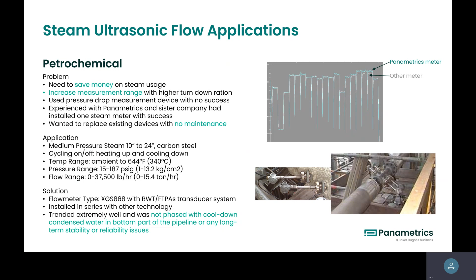And with it, you can see the design we used with our BWT technology. It was a 2-pass system because accuracy and reliability are so important to them. They wanted to have redundancy overall. So it gave them the capability of, hey, I don't want to touch it anymore. Even if I can compare 1 versus 2, there are a lot of diagnostics and measurements you can do beyond just the flow measurement. In this situation, you can see the temperatures and pressures, 15 to about 190 pounds of pressure. But actually, because this one kept cycling through, it was cooling down and condensing on the bottom, and it wasn't really steady state. That caused a lot of problems with existing technology as well, whereas ultrasonics can handle that rangeability from shutdown to startup.